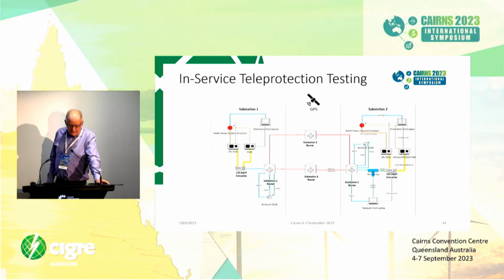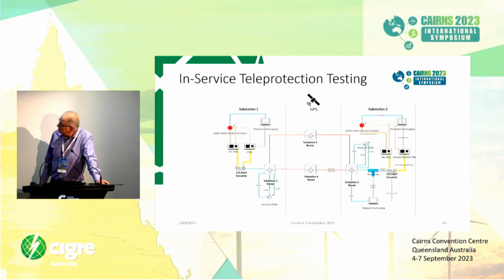So this diagram just shows the overall teleprotection testing setup. Firstly, on the power system side, we've got a couple of protection relays with a Doble injection test set at both ends. Doble's one brand, you can use Omicron as well. It's just a protection injection test set. You've got a protection test laptop connected to the protection relays, and also the power system simulator, that injection test set. Then on the communication side, we've got some packet injection test sets, some Y.1564 test sets connected into our two routers at substation 1 and 2, which allow us to inject simulation traffic for teleprotection, but also importantly, we also want to inject background traffic.